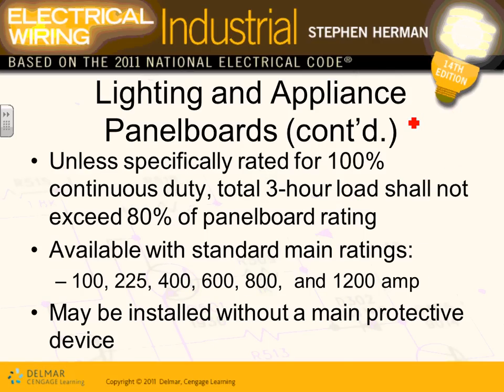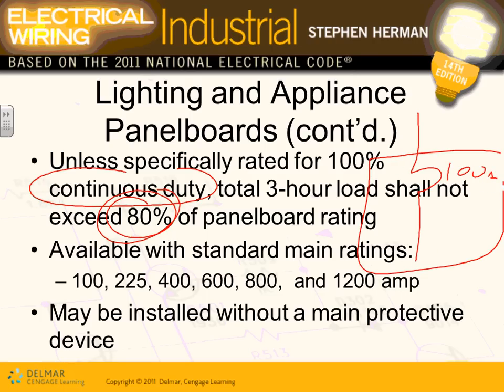Panels, guys, are rated. Panels through their circuit breakers, when they're carrying continuous duty, they are rated for 80%. What does that mean? When they have a 100 amp panel, this means load-wise, the continuous load that I can pull is only 80 amps. If you have a 100 amp panel and a continuous load like lights, you can only pull 80 amps out of the 100 amp panel based on the 80% rating, unless they are 100% rated equipment.